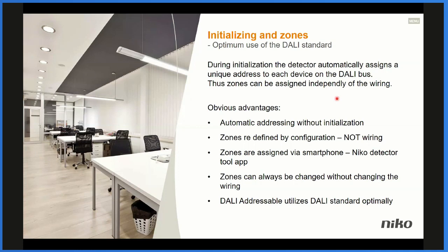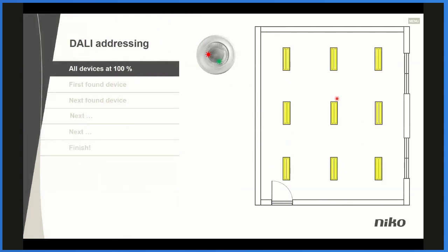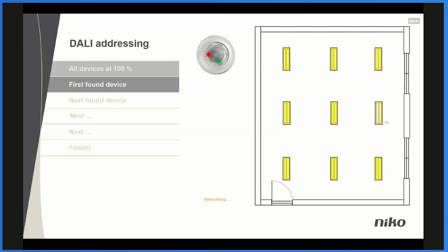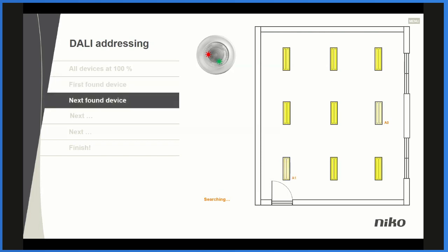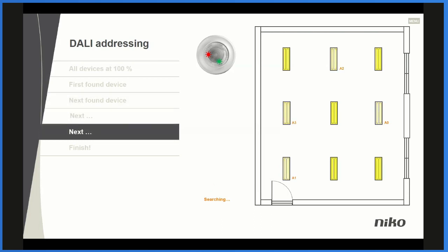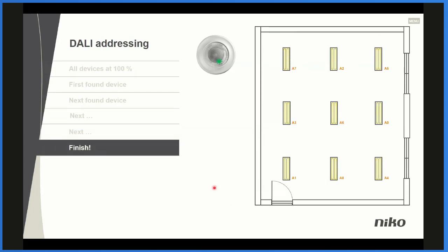So with DALI addressable, we utilize the DALI standard optimally. When you have to initialize and do the commissioning, the detector will show that by flashing red and green, and it automatically starts with one device. All luminaires will light at 100%, and when one device is found and given an address, it will be shut off or dimmed down. Then the next device is also given an address, and that's done automatically, and it will continue until all the devices are given an address.